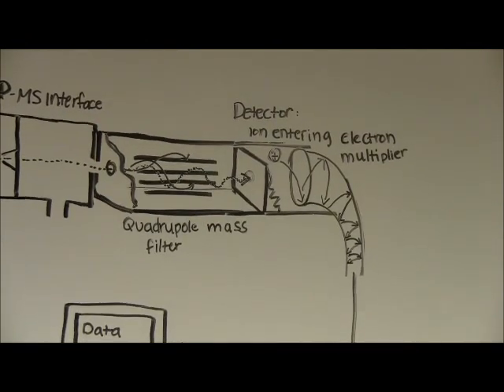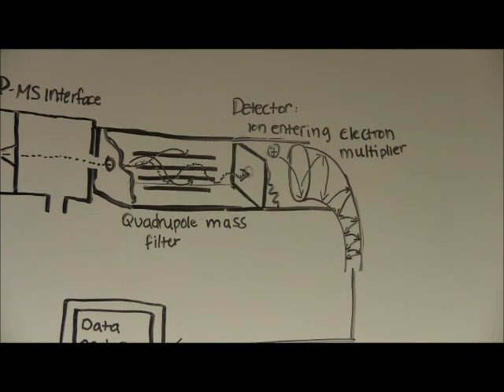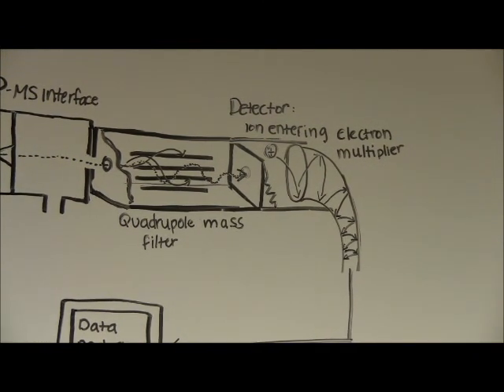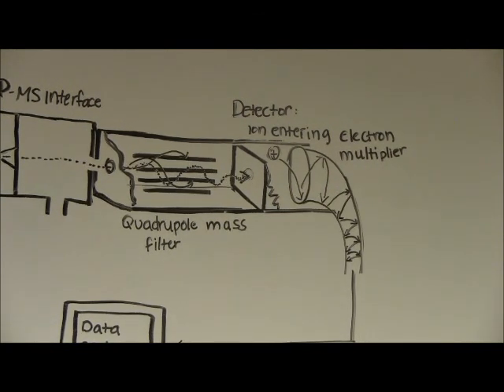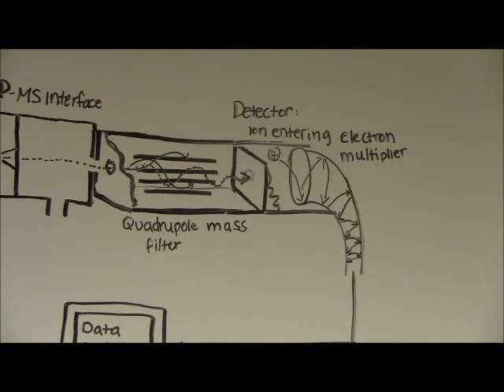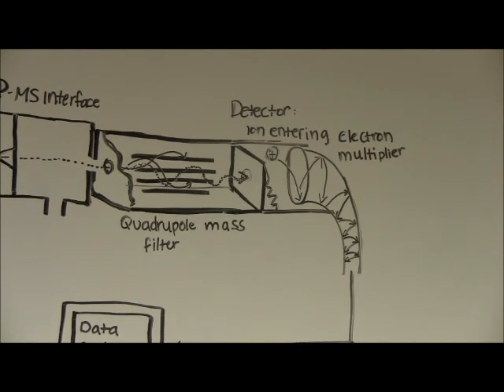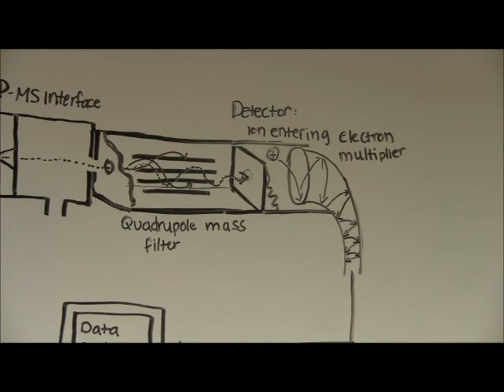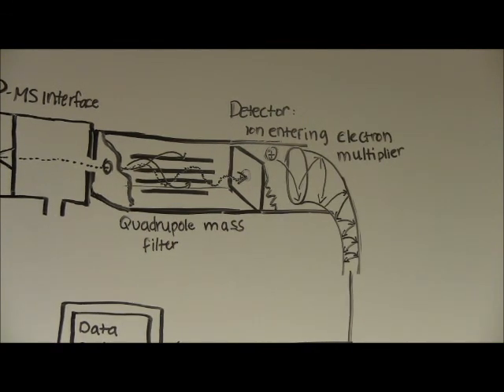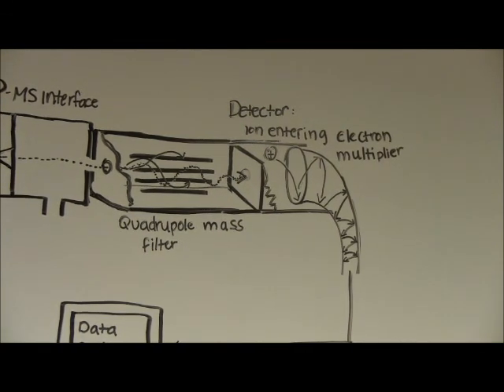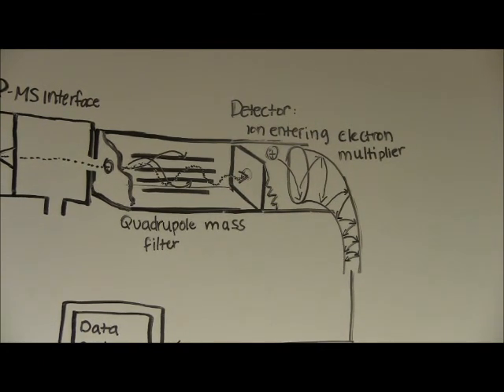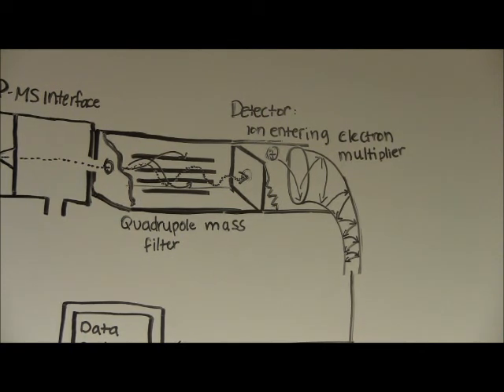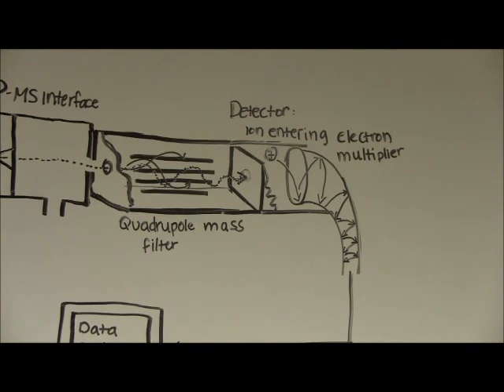The most common type of ion detector found in an ICP-MS system is a channel electron multiplier. This cone or horn shaped tube has a high voltage applied opposite the charge of the ions being detected. Ions exiting the quadrupole are attracted to the interior cone surface. When they strike the surface, additional secondary electrons are emitted, which move further into the tube emitting additional secondary electrons. As the process continues, even more electrons are formed, resulting in as many as 100 million electrons at the other end of the tube after one ion strikes the entrance of the cone.